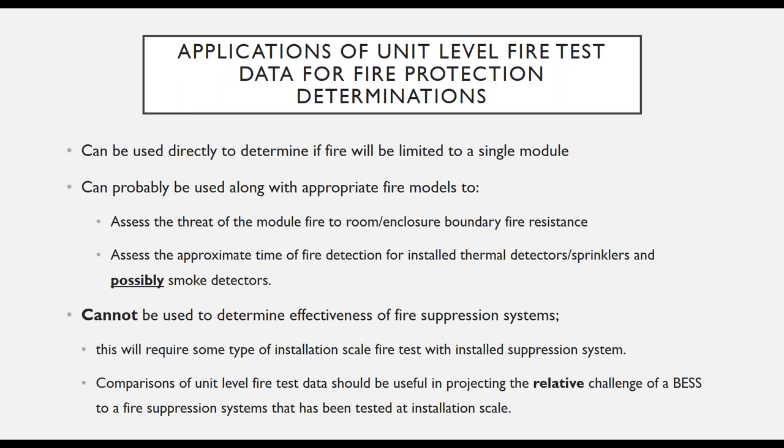And most of the time, in most cases, it cannot be used to determine the effectiveness of fire suppression systems. In order to make that determination, an installation scale fire test with an actual installed suppression system will be required. However, as the last bullet says, the comparisons of the unit level fire test data from different tests should be useful in projecting the relative challenge of a BESS to a fire suppression system that has been tested at installation scale.